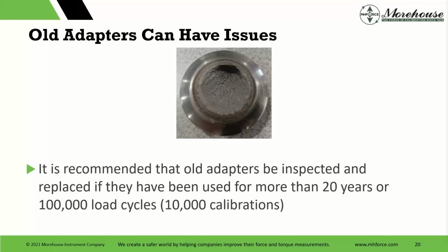But even here, with calculation and test, this is an old adapter that broke. It's ours. The source of the break was that the machinist actually took a little bit too much of an undercut, and we did not have a 2-to-1 safety factor. So it failed a little bit early. And the top, it's a grade 8 bolt, and it failed, we were estimating, after about 350,000 load cycles. New adapters are designed for a life cycle of at least 500,000. And that's what we should have expected from this one. I mean, eventually it would have fatigued and broke. That's about 50,000 calibrations, and failure at close to 1 million load cycles.